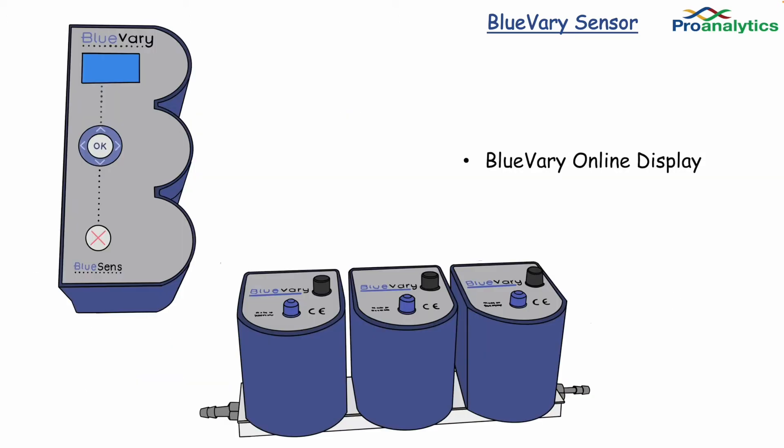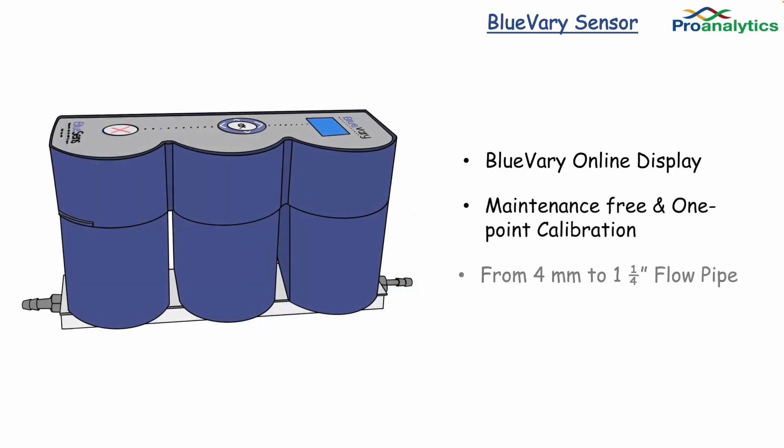The BlueVary display unit fits over the cartridges, allowing for visual readings during the run. Depending on the application, gas sensor cartridges can be chosen and exchanged with minimal effort. The BlueVary is designed to be maintenance-free due to exchangeable cartridges — just change on a yearly basis.